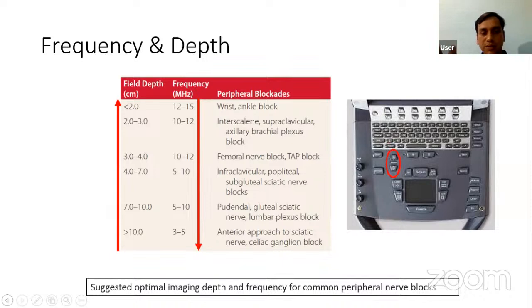I'm just giving an example here of how depth and frequency matter when you are doing a peripheral nerve blockade. For superficial structures, as you know, you have to keep a very high frequency and set a very low depth. As the depth increases, as you can see, the frequency also goes down. And there is a dedicated button on this M-Turbo Sonosite machine where you can increase and decrease the depth.